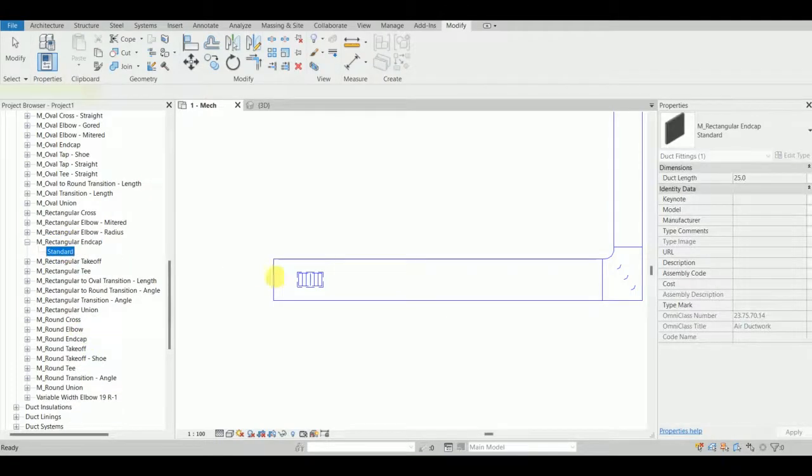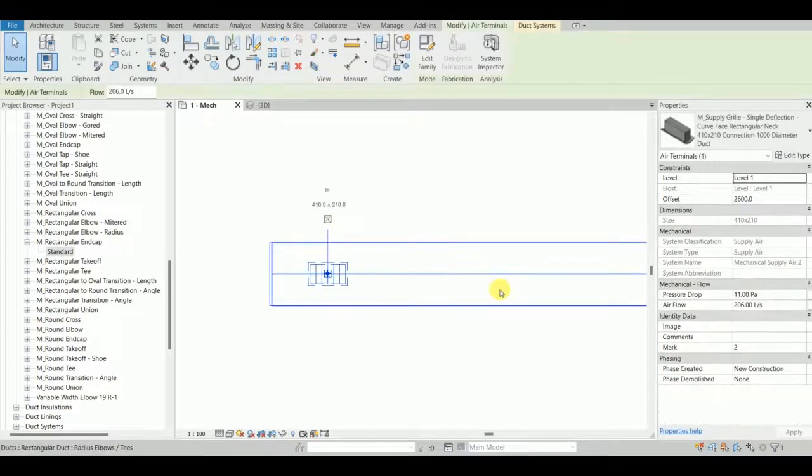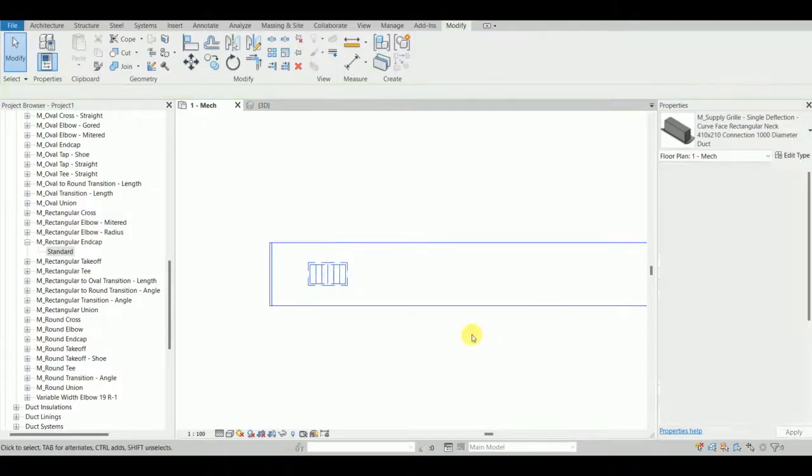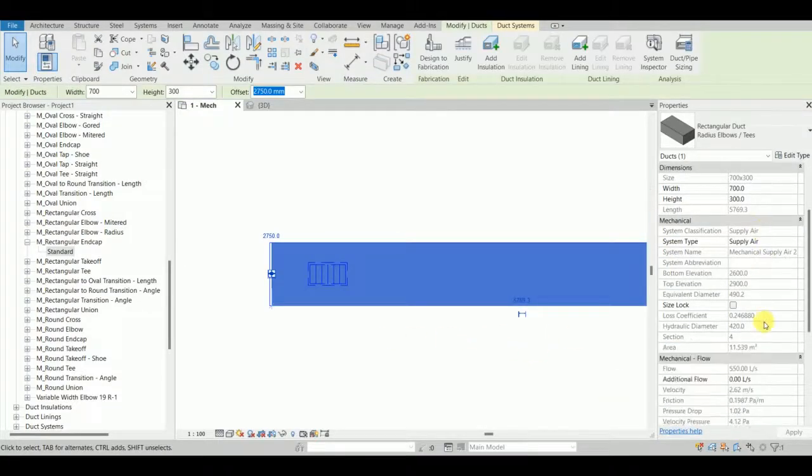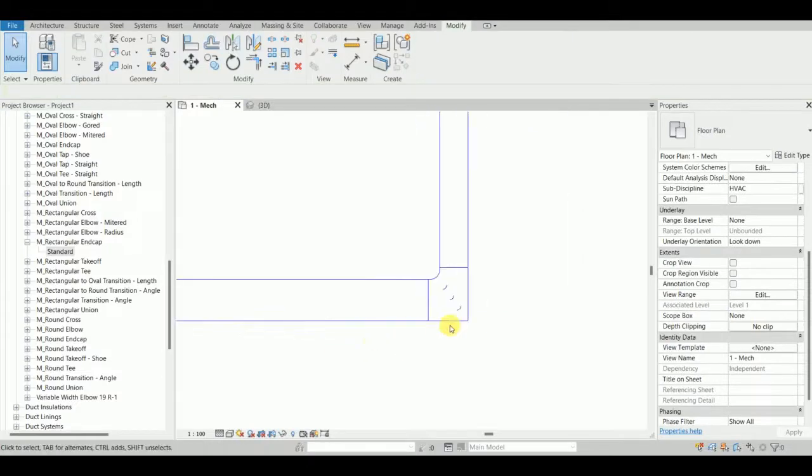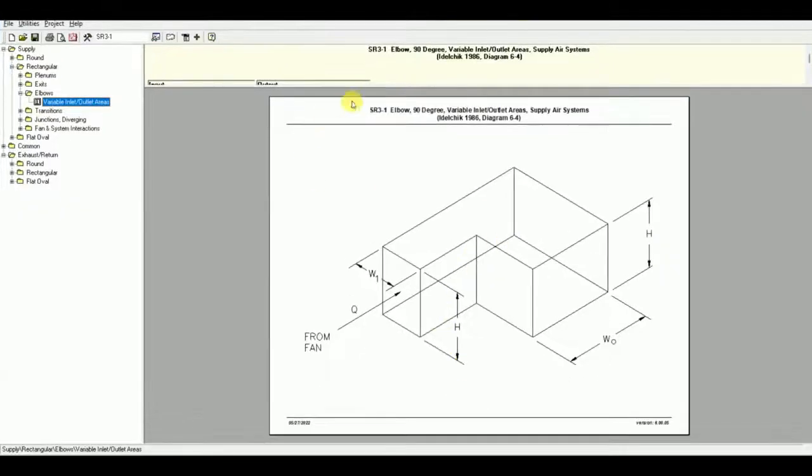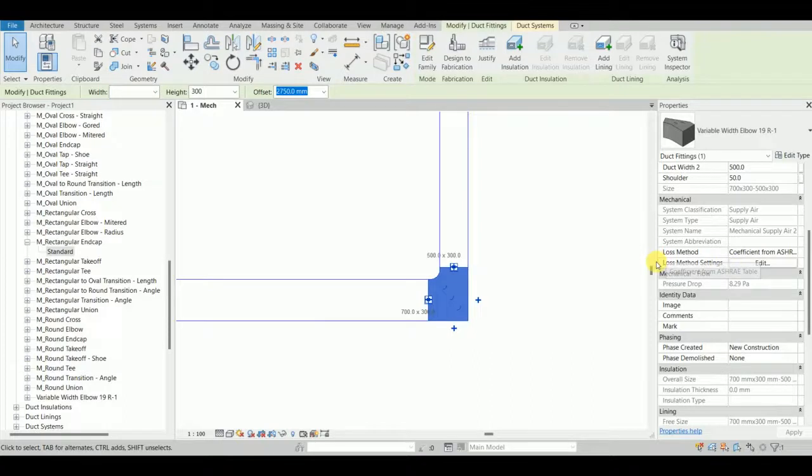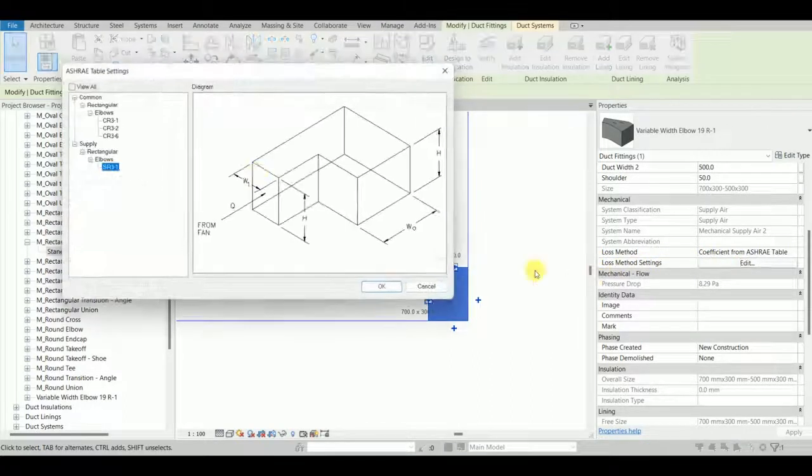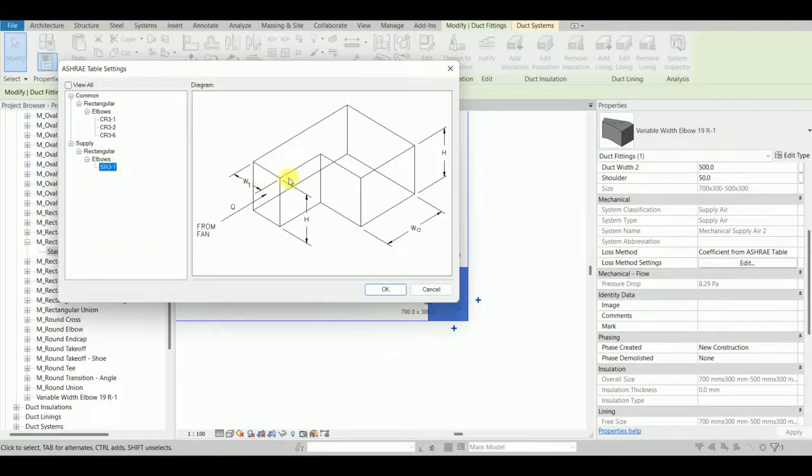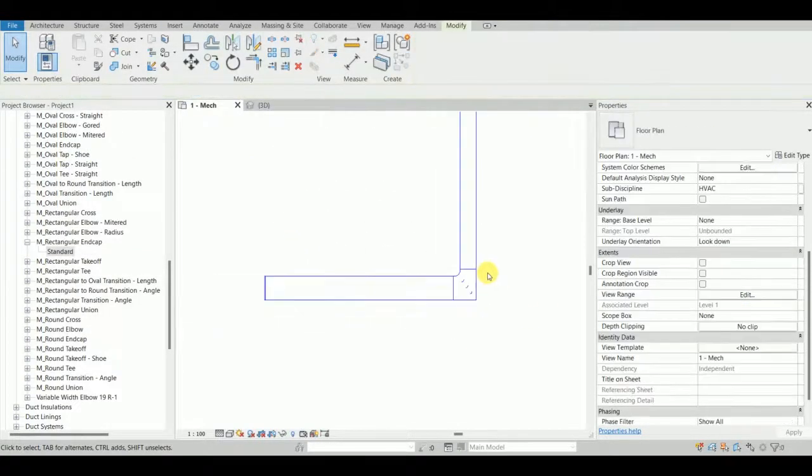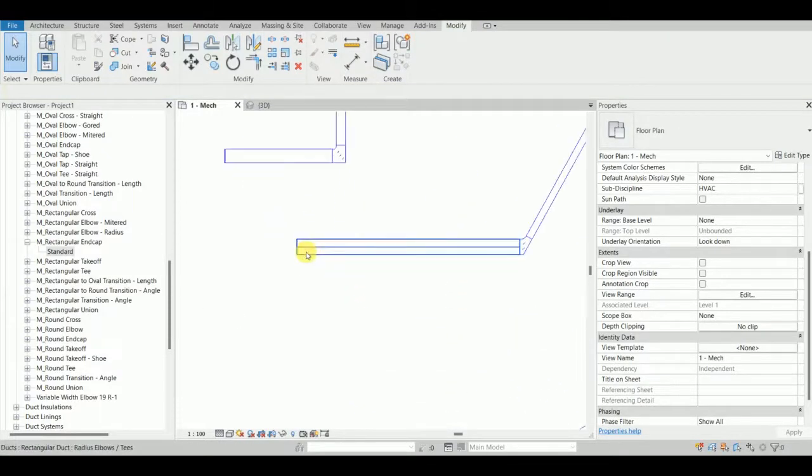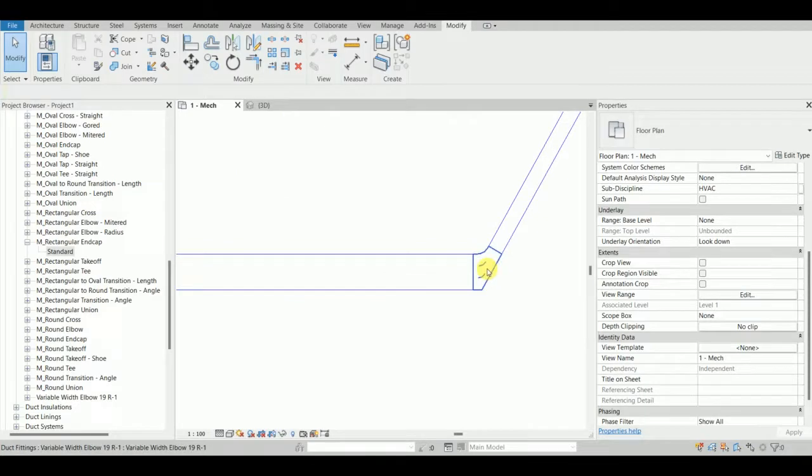I'll give some value - let's say 550 liters per second. Initially I showed you this table SR 3-1. The loss method settings show SR 3-1, and it is 8.29 pascals. That's good enough.